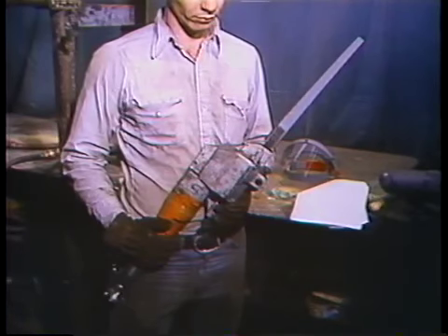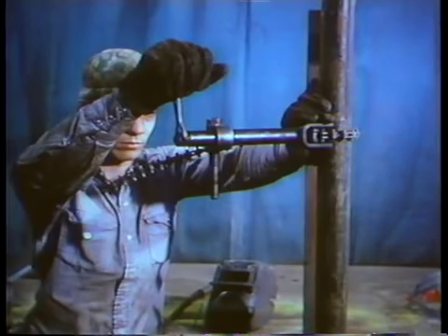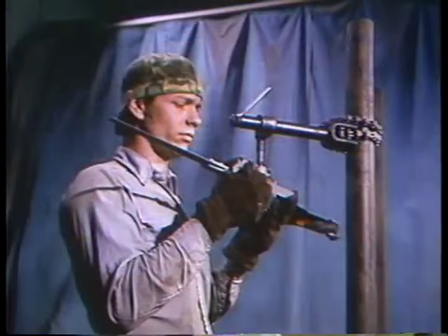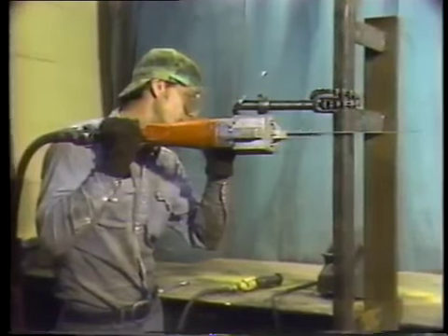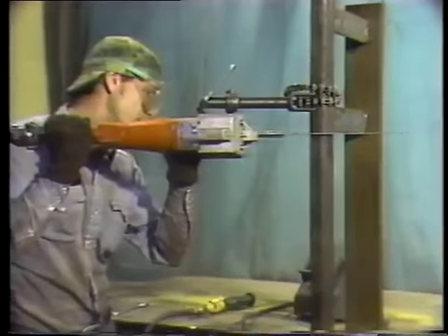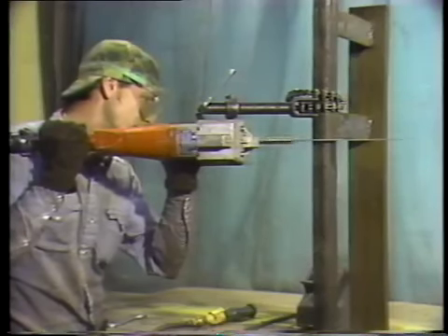Now, this type of saw is attached to the tube that will be cut. This is done by attaching a clamp to the tube and then attaching the saw to the clamp. Cutting is done with a saw rather than a cutting torch to avoid getting slag inside the tube. Two cuts must be made to the damaged tube section, one above the failure and one below.